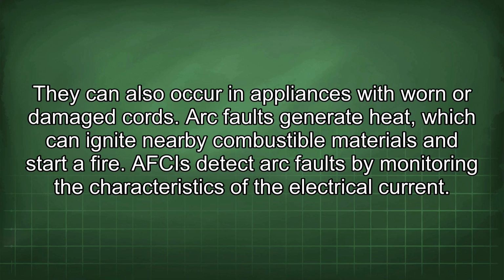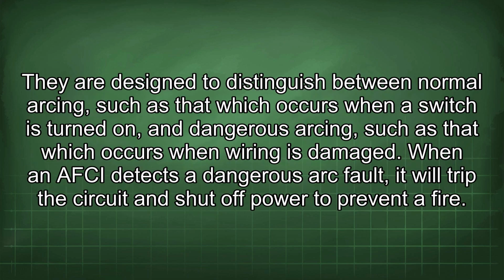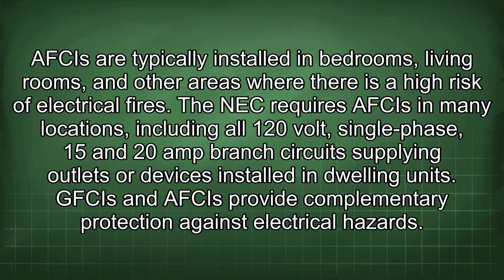AFCIs detect arc faults by monitoring the characteristics of the electrical current. They are designed to distinguish between normal arcing, such as that which occurs when a switch is turned on, and dangerous arcing, such as that which occurs when wiring is damaged. When an AFCI detects a dangerous arc fault, it will trip the circuit and shut off power to prevent a fire. AFCIs are typically installed in bedrooms, living rooms, and other areas where there is a high risk of electrical fires. The NEC requires AFCIs in many locations, including all 120-volt, single-phase, 15 and 20 amp branch circuits supplying outlets or devices installed in dwelling units.